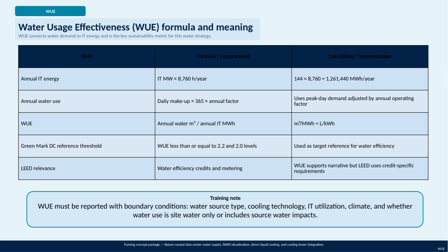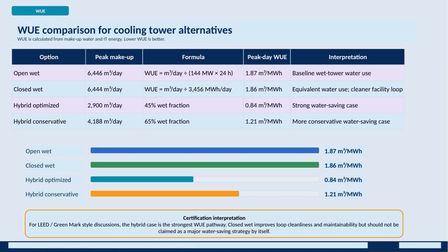Here we have a comparison of water usage effectiveness, or WUE, for different cooling tower alternatives at the Batam Coastal Data Center. WUE is calculated by dividing the peak makeup water usage by the IT energy consumption measured in megawatt hours. Essentially, a lower WUE means better water efficiency. Starting with the open wet cooling tower, we see a peak makeup water use of around 6,446 cubic meters per day, resulting in a WUE of 1.87 cubic meters per megawatt hour. This serves as our baseline for comparison. The closed wet system uses a similar amount of water, about 6,444 cubic meters per day, but offers a slightly better WUE of 1.86.